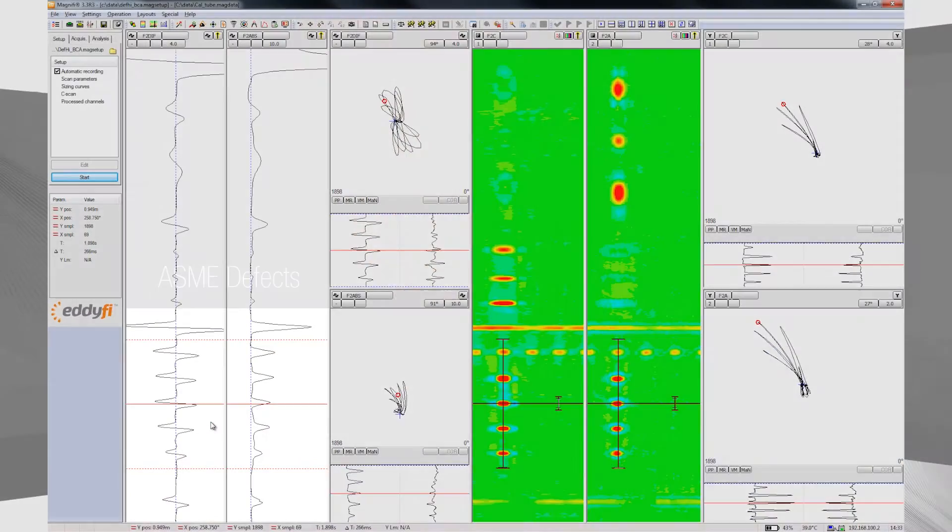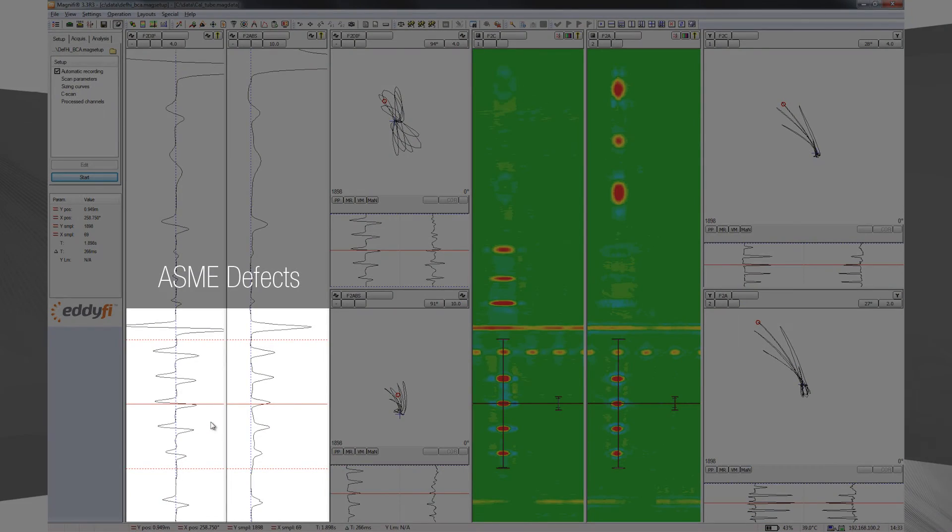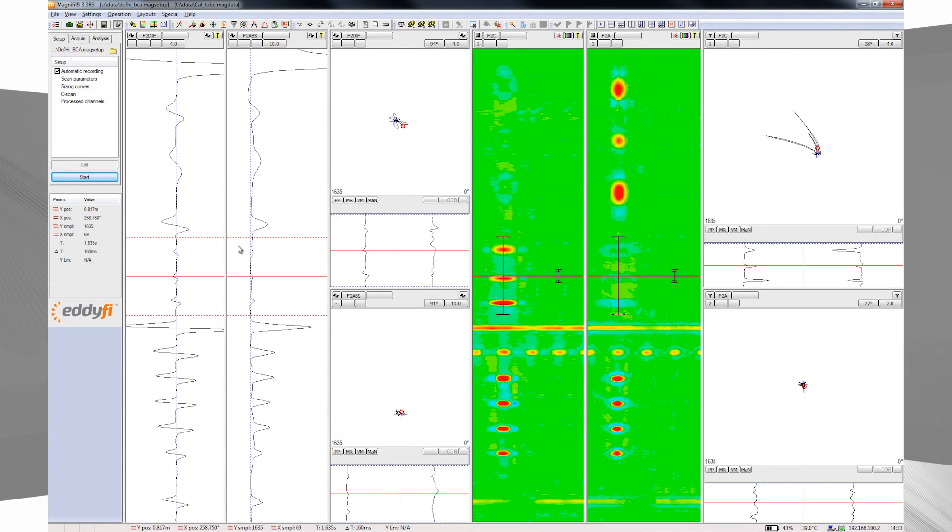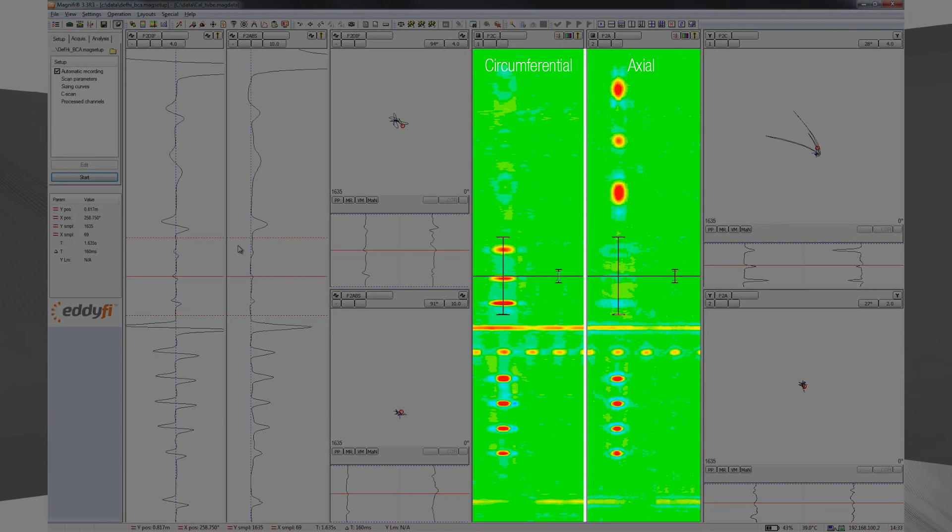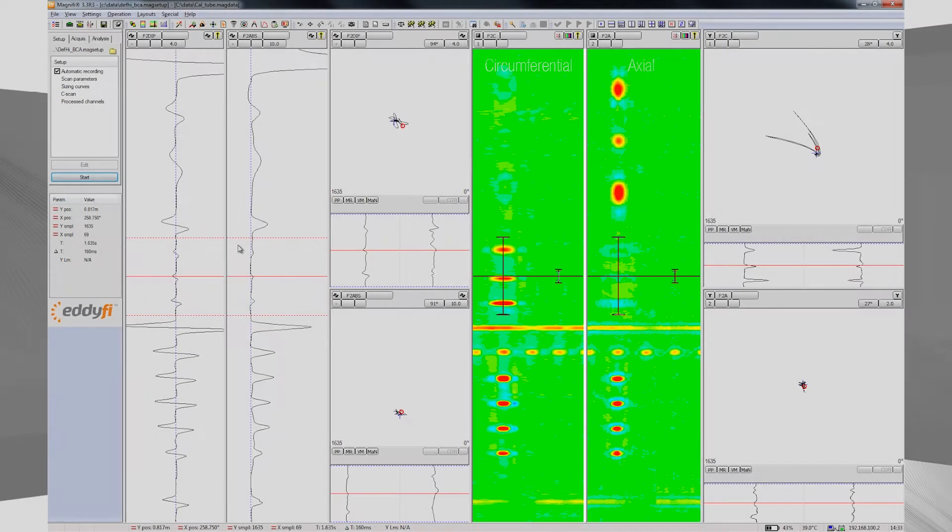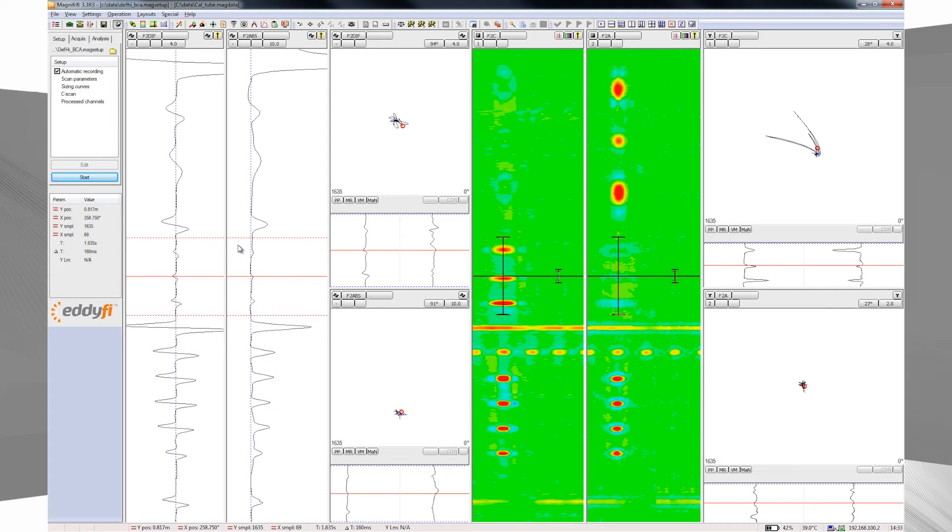As you can see, Magnifi displays standard ASME defects detected with the bobbin probe. But you can also see that the array yields very clear imaging of the axial and circumferential crack-like defects in the form of an easy-to-read C-scan.